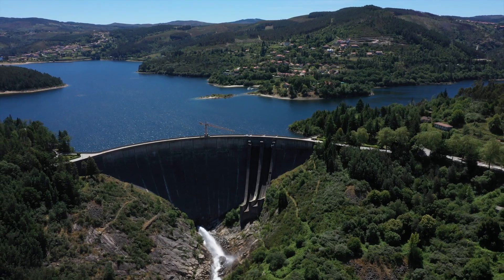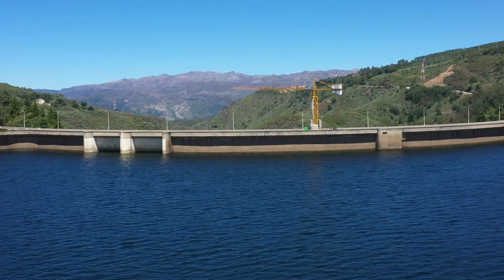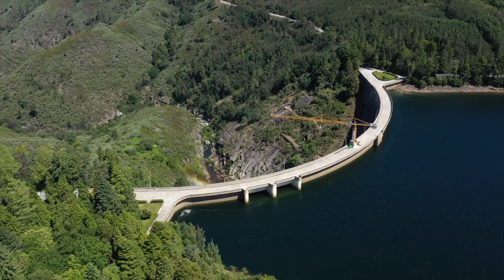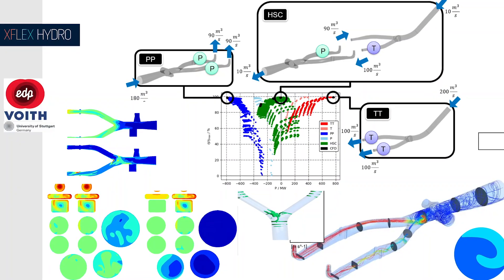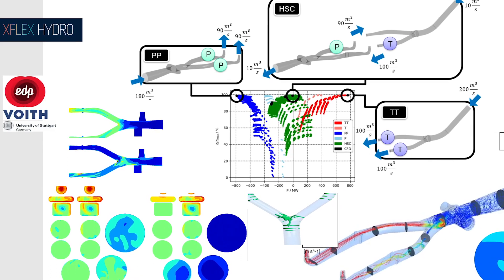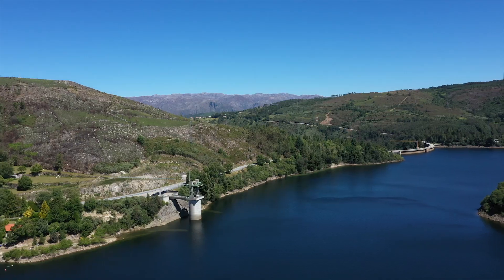The new hydraulic short circuit power plant operation will result in different flow conditions of the main water system, which could potentially cause safety issues. So we need to use digital modeling and computer simulations to investigate how the plant will behave under these different conditions. A series of analyses must be performed, including pressure surge analysis, flow field simulations, and stress analysis of the most sensitive areas of the plant.